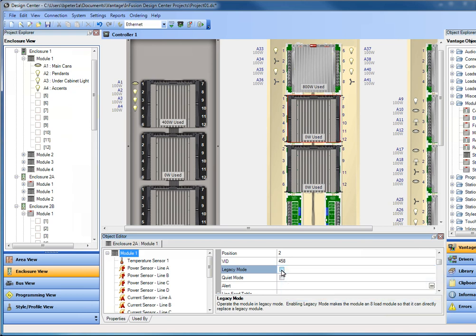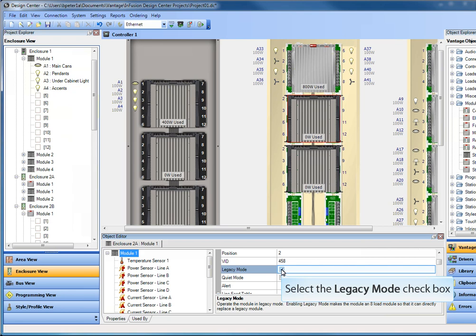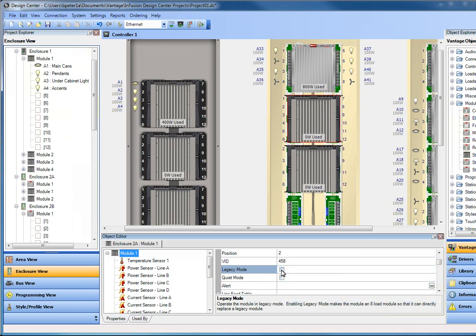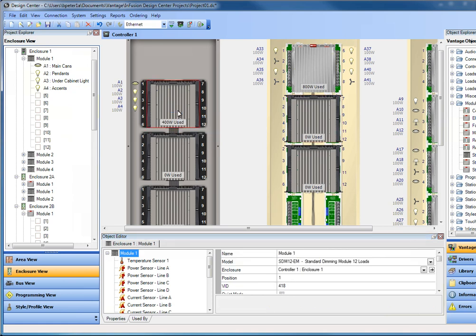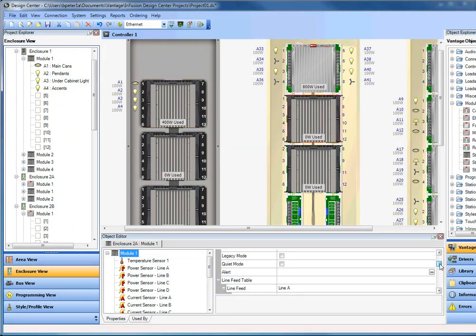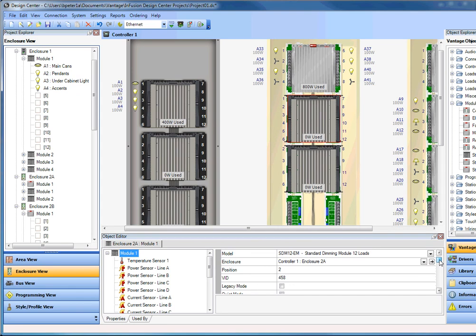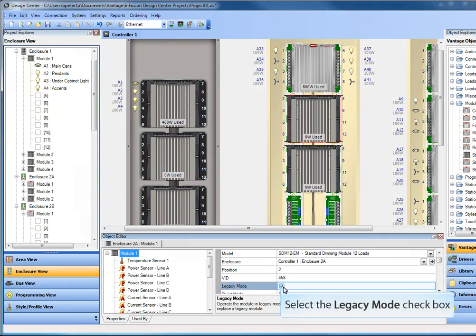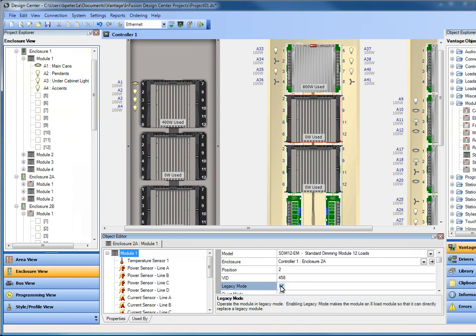So something to keep in mind when you're working with legacy enclosures is the legacy mode option on the module, which will change the number of line feeds and loads and the terminal boards that will ship for that particular module in that position that will need to be installed in that legacy enclosure. So there we reviewed two things: one where we added a new enclosure and a new set of modules and needed to drag across all of our loads, or create a new enclosure for existing modules and just drag the modules over. Or in the second example where we have a legacy enclosure and we have new modules that need to be positioned, we learned about the specific legacy mode which will allow me, as an installer, to separate between either four loads and one line feed per side or six loads and two line feeds per side and ship me different terminal boards based on what I'm trying to do.